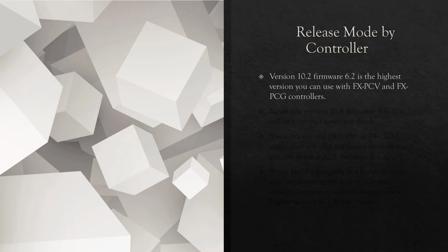All right, release mode. So you can only use version 10.2, firmware 6.2 on the older FX PCV and PCG controllers. That's as high as they'll go up to.